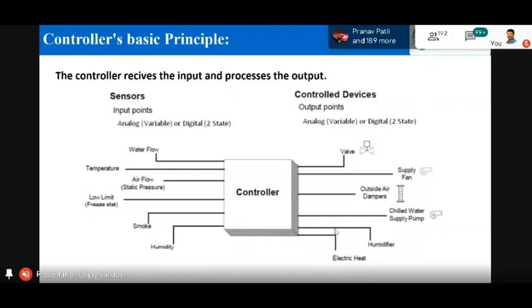This is a very, very basic principle of any controller. This is for those who do not have so much idea about instrumentation. So you have sensors, controllers, and outputs. Sensors give you input. If it is temperature, there will be a sensor like an RTD, which will give you variable resistance as a measurement of temperature. It goes to the controller. Controller has an algorithm. It could be just on-off. It could be PID. It could be whatever it is. And then the process signal goes out and it drives the valve or a supply fan or dampers or VFD. So this is a very standard controller.